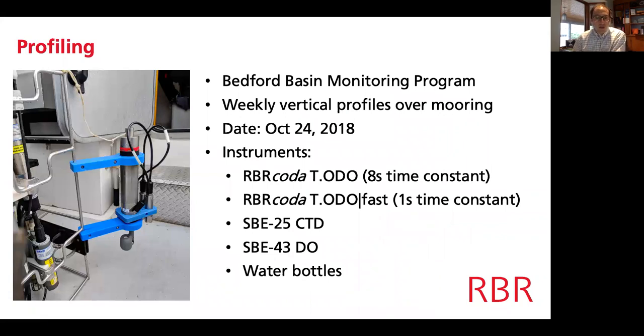And then a couple months later in October, on October 24th, RBR showed up and joined one of the cruises that DFO runs. So they maintain a Bedford Basin monitoring program, which goes out weekly on Bedford Basin and does a bunch of CTD casts. And one of the casts is directly over the mooring location. So we joined them on October 24th, and on this cruise, we put an RBR CTD with 2 CODA T.ODO oxygen sensors. One was the standard with an 8-second time constant, and the other was the fast with the 1-second time constant. Also on this CTD was a Seabird 25 CTD with the Seabird 43 oxygen sensor and water bottles.